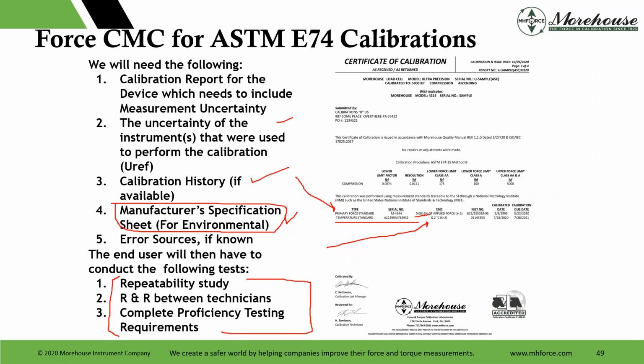Highly recommended. There's times we get load cells in our lab and they're just not working right. And we're like, is it us? Is it the machine? And having that check standard, you put it up in and say, nope, not us. It's that, right? Without that check standard, you really can't point to it. And you want to make sure you're maintaining. Different things happen. What if a tech changes out an adapter? With the check standard, you can check different adapters there too.